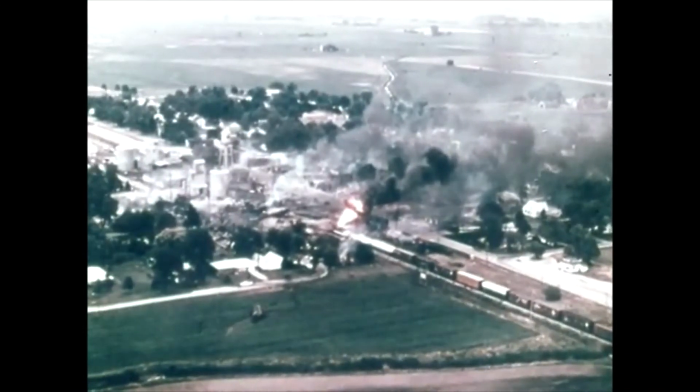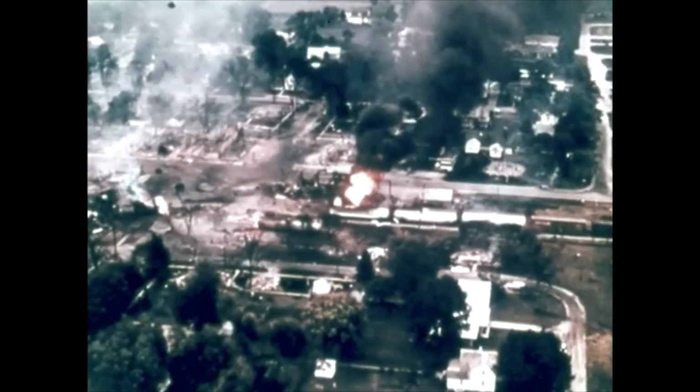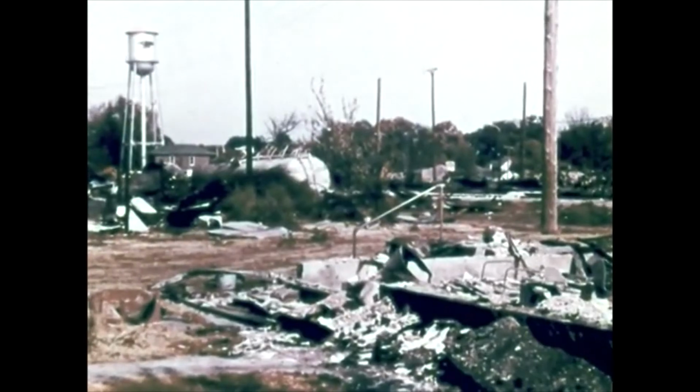At Crescent City, life and property exposure was high. Tank contents were not immediately known, and water for cooling was not available. The pileup of tanks multiplied the BLEVE hazard. Only by the quick evacuation of civilians and the judicious retreat of the fire forces was loss of life avoided.